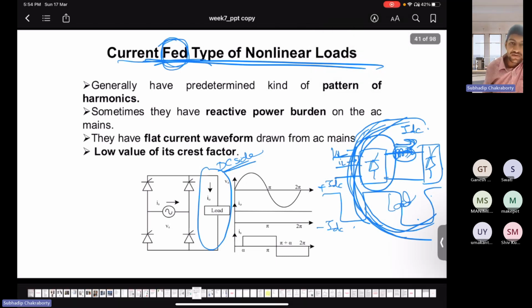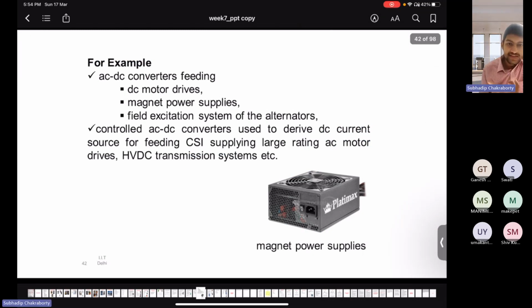You need to understand that, because in the passive power filters and their classifications, what type of compensating filters we use to mitigate the harmonics, series or shunt, will be decided by the nature of the loads. When we come there, you will see how the use of those filters differs with the nature of the loads. That's why understanding the nature of the load is very important at first. Whether my load is nonlinear or linear. Then, once I have sorted out that my load is nonlinear, what kind of nonlinearity? That is, whether the load is current fed or voltage fed. That is also important. After understanding all these steps, we'll move on to the selection of the filters and compensating devices that we already discussed in week 2. So understanding your load is very important from a grid operator's perspective.